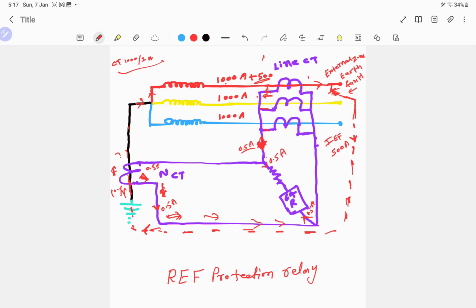So 0.5 ampere comes from the line CTs because of the unbalanced load in the R phase CT, and the 500 ampere sensed here at the neutral CT will result in 0.5 ampere flowing through the neutral CT secondary. That will be in the opposite direction of the line CT. So both similar currents in opposite directions will cancel, the resultant current will be zero, and the relay will not operate.